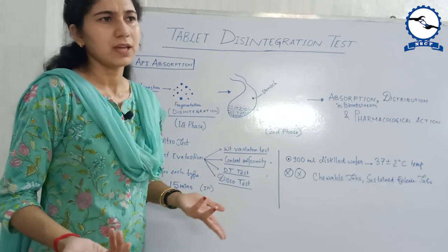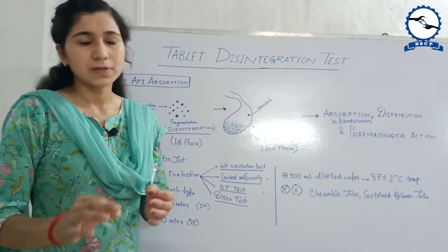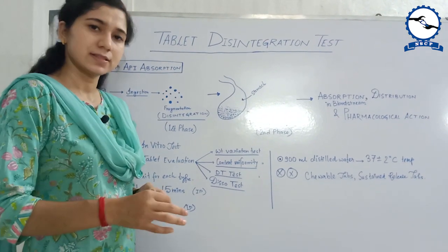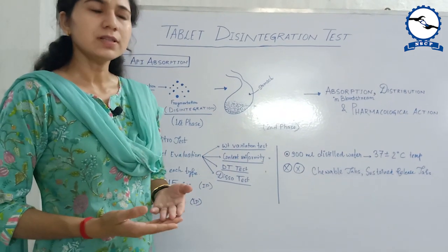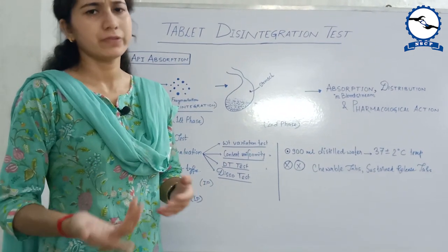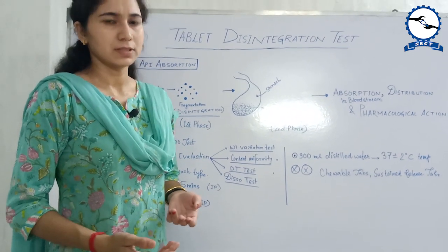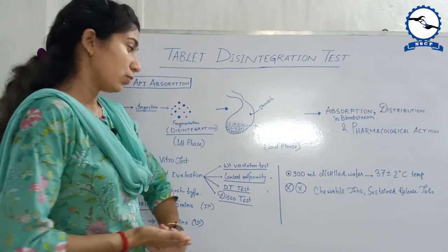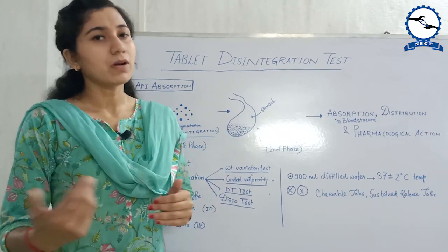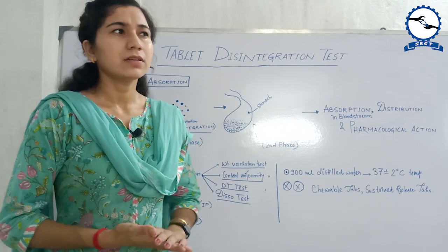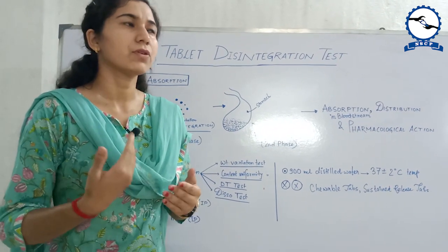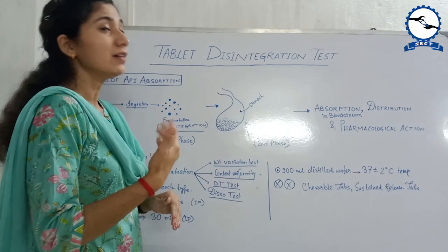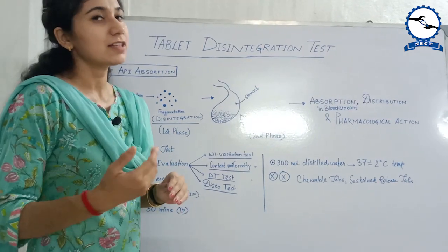Each tablet has a specific disintegration time — the coated tablet will obviously take more time and the uncoated tablet will take less time. In the IP, it is mentioned that the uncoated tablet generally takes about 15 minutes and the coated tablet generally takes about 30 minutes, but it increases for enteric coated and other types of coating. Also, this test cannot be done for chewable tablets or sustained release tablets. Now let us move on to the DT test apparatus and we will be seeing a small demo.